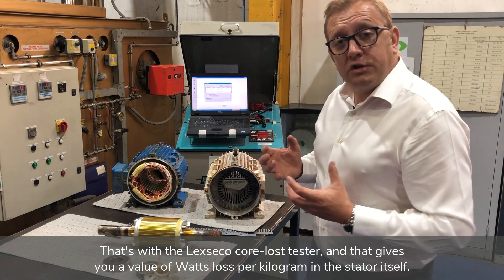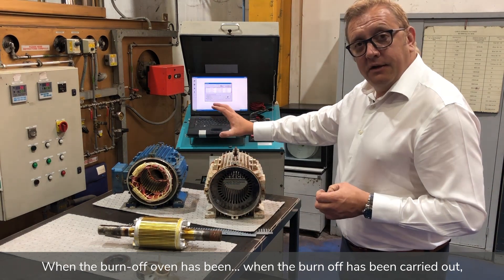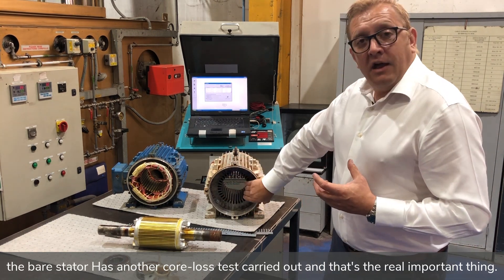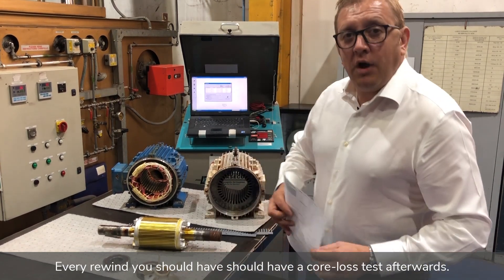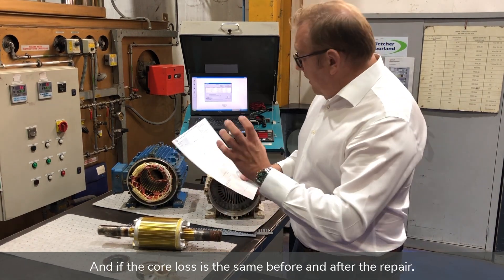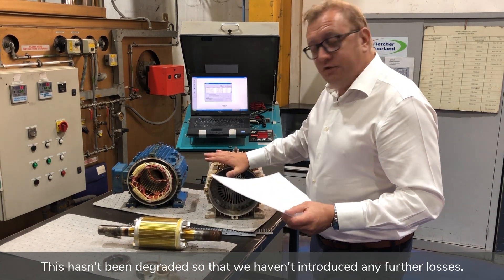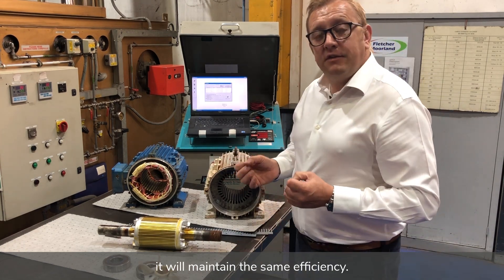The core loss tester gives you a value of Watts loss per kilogram in the stator itself. When the burn-off has been carried out — again, no more than 370 degrees C — the bare stator has another core loss test carried out. This is the really important thing: every rewind should have a core loss test afterwards. If the core loss is the same before and after the repair, the lamination coating hasn't been degraded, so we haven't introduced any further losses, and when the motor is rewound and rebuilt it will maintain the same efficiency.